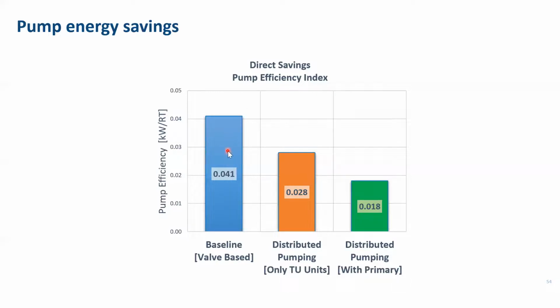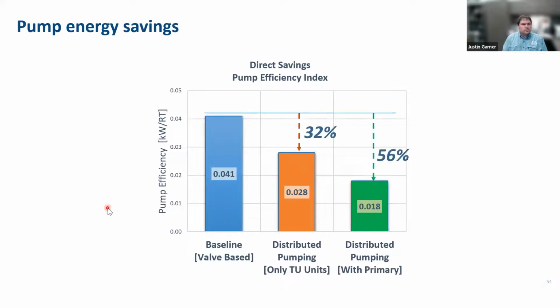So you can see as we went from our baseline system to just changing out the distributed pumps, we had an improvement from 0.041 kW per ton to 0.028 kW per ton with those distributed pumps alone. Once we combined the two and right-sized, or downsized, the primary set to match the distributed pumps, we were able to get down to 0.018 kW per ton, which is ideally where you'd want a system like this to be tracking. And again, in terms of pump energy, we saw a 56% reduction in energy on that system.